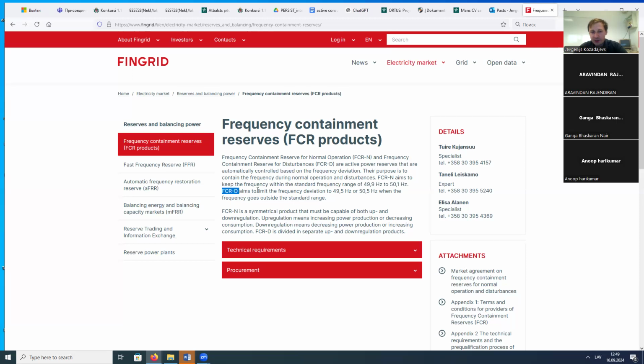And FCR-D - in this range we can consider there is no deviation, it is normal operation, no deviation. FCR-D aims to limit the frequency deviation from 49.5 to 50.5 Hz when the frequency goes outside the standard range. See, this is standard range, this is outside the standard range.